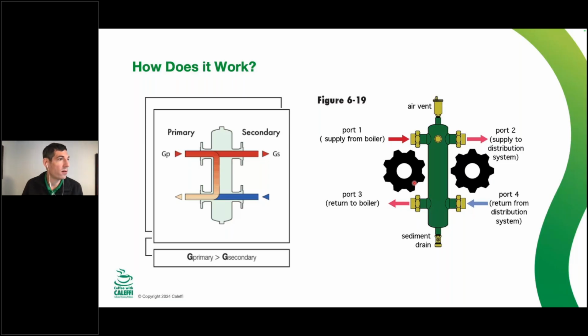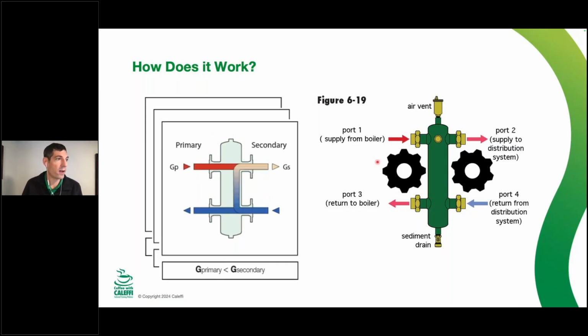So the third example is the opposite of that. We've got the boiler spinning at 10 GPM again, and now let's say we have fan coils or something that has a smaller delta T from the supply to the return out to the system. In that case, we may be moving the same amount of BTUs across here, but this needs to move faster. We're going to have a smaller delta T here. It could be very different if you had a 40-degree delta T across some sort of radiant installation versus a 3-degree delta T for another application. If you're doing something like radiant cooling, you might have a really, really small delta T. And in that case, this is going to be moving a lot faster than the one on the left, even if the number of BTUs exchanged is similar.